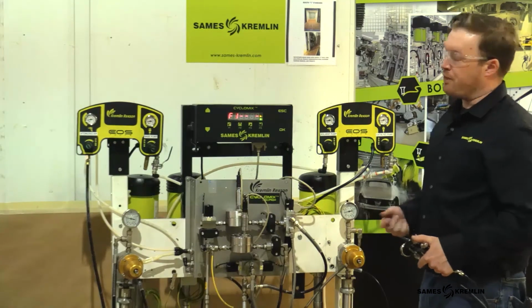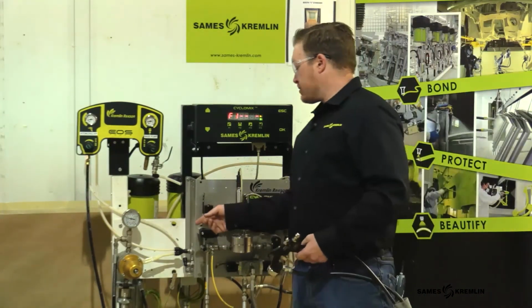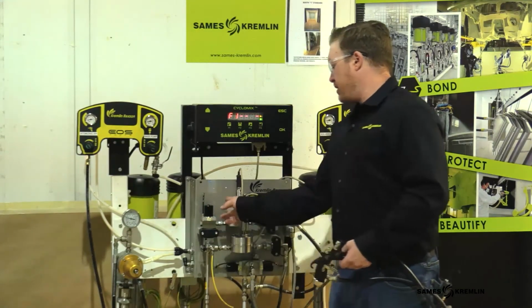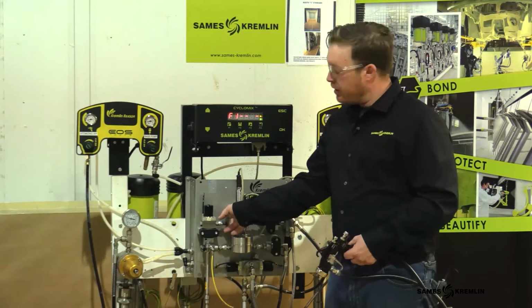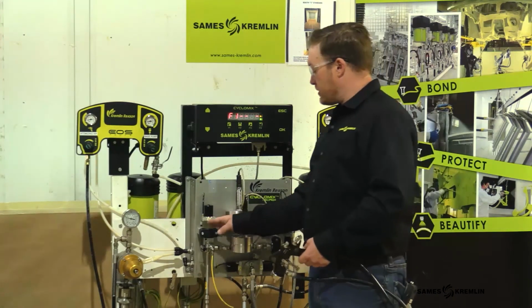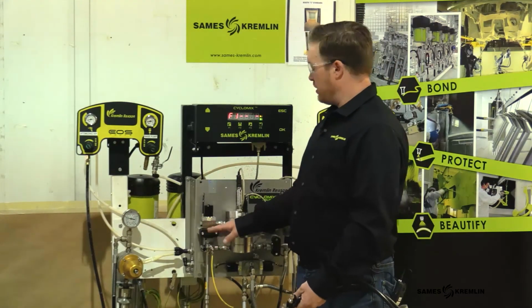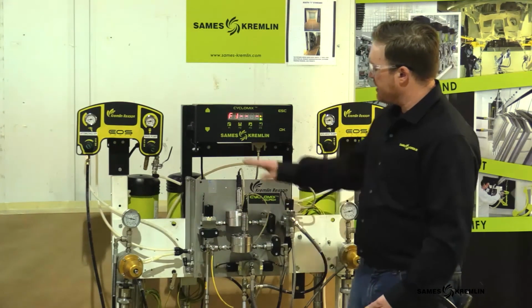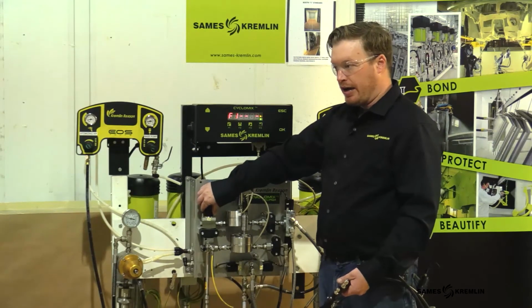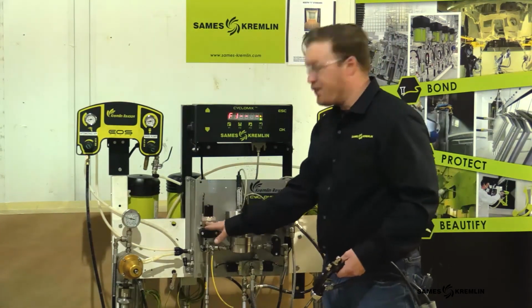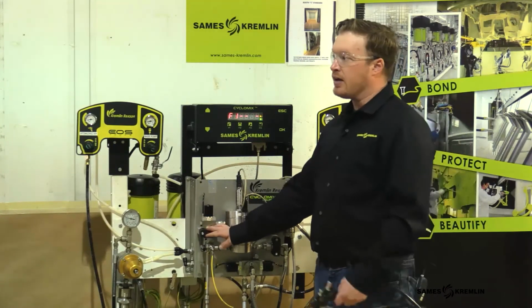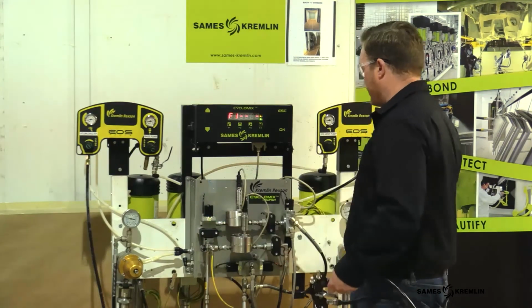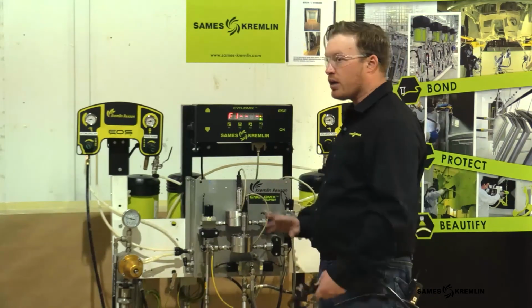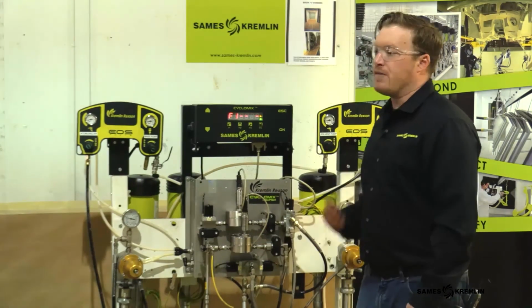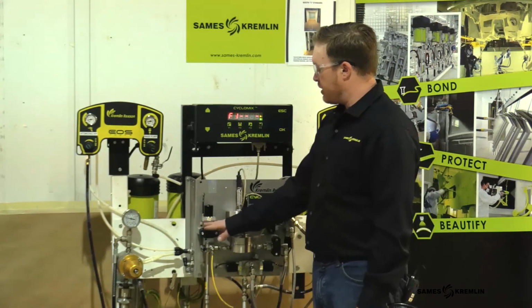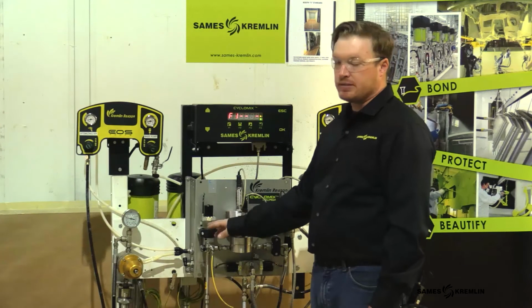So from there we go to error 5. Now error 5 is where we see pulses from the catalyst flow meter when we're not supposed to. So that's going to tell us that the valve is leaking here. Now that is going to be your most common error, or fix, basically. When you see an error 5 and it's reoccurring, and you know that there is no more air in the system and the system's been running, and you start getting error 5s, that's telling you that there might be some catalyst seeping past this VP6 valve.